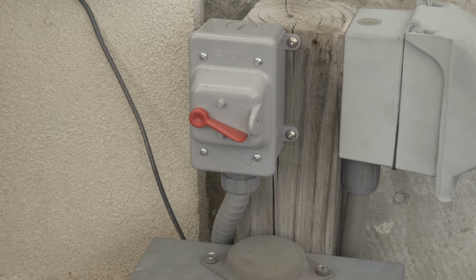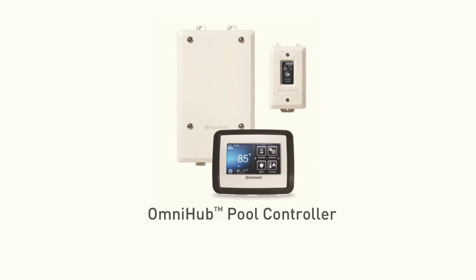If a light switch already exists, is mounted in a single gang box, and is within 15 feet of the equipment pad, then the smart relay can simply replace the manual switch. Otherwise, the single gang box that comes with the smart relay must be used. Make sure the wiring hub is within 6 feet of the pump.